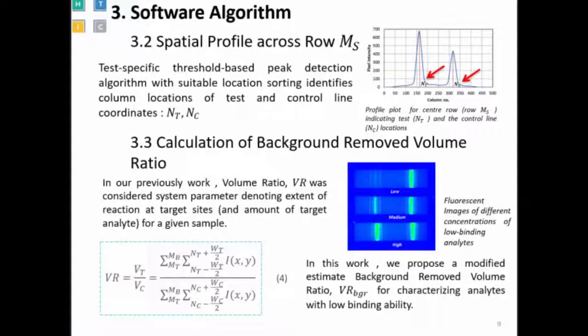The VR equation is the summation of the entire test line area divided by the summation of the control line area. You can see test lines from cartridges at different TSH concentrations — high, medium, and low. However, TSH suffers from a lower dynamic range, where a large background is also present. The light blue area represents this background, which gets added in with the test and control line signals. We designed an algorithm to remove that background.